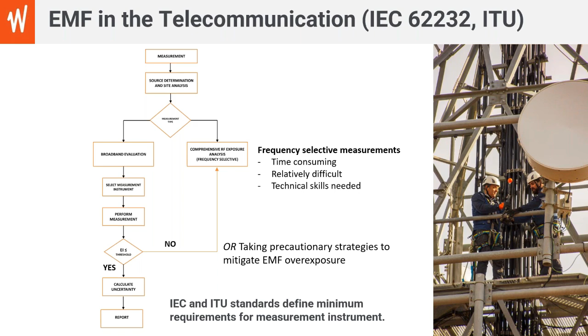Then also in telecommunications applications, here's an example of 5G measurements using a broadband device. So in this case, the SMP3 meter and a WPF probe. The WPF probes have different selections. They cover the FR1 and the FR2 bands for 5G applications, allowing you to cover these kinds of applications. So in this example, what the operator did was use a mobile device to draw traffic towards the SMP device to measure the maximum field levels. This is also one of the strategies for measuring 5G applications as defined by the standards.